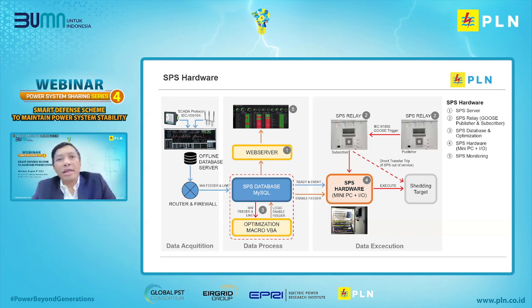The feeder data ready for load shedding is sent to the SPS hardware in the form of a mini PC, plus an input-output module to prepare the feeder to be executed when a contingency occurs. When a contingency occurs, the SPS relay publisher will send a trigger signal, using the GOOSE protocol, to the SPS relay subscriber to execute the feeder previously prepared by the SPS server.